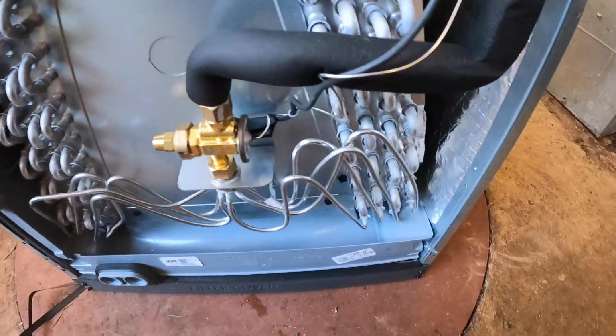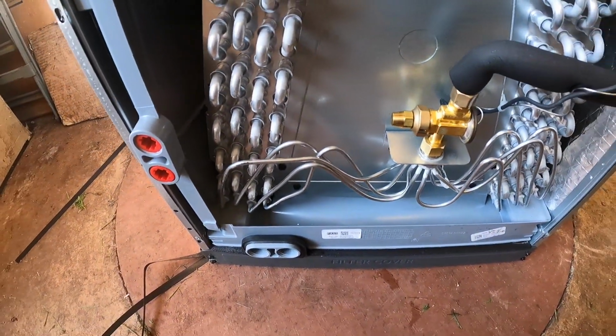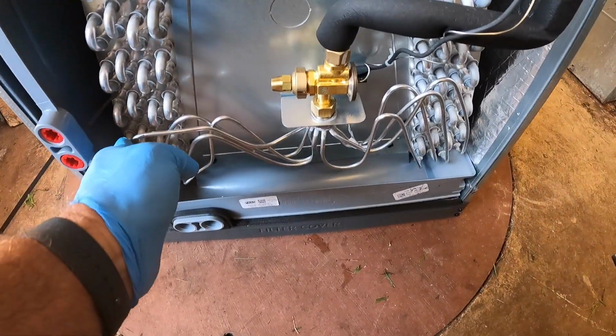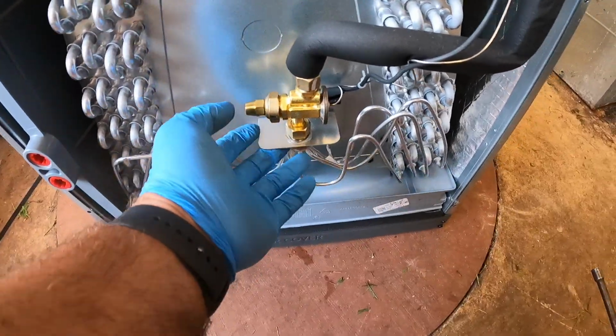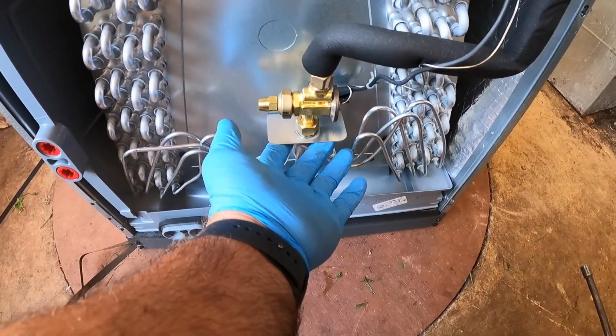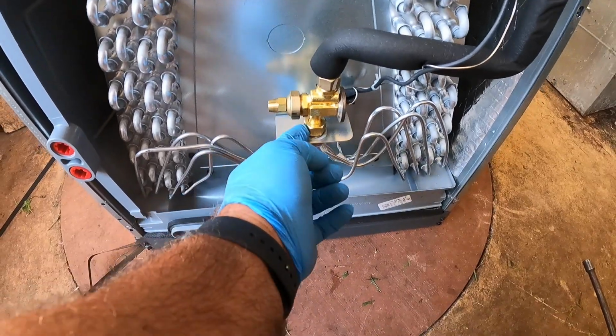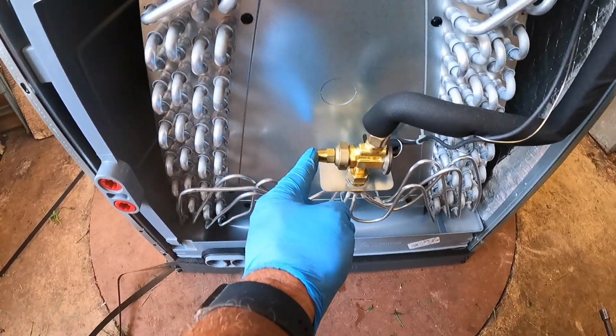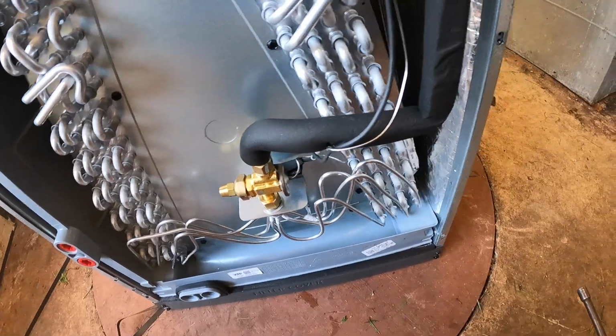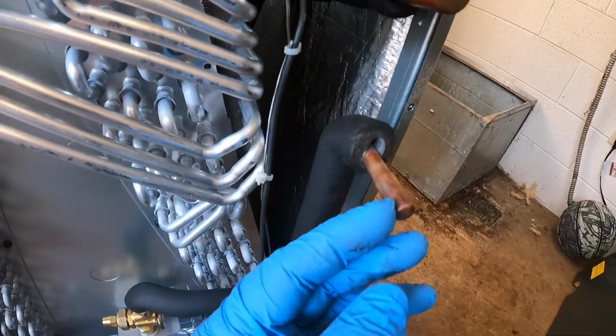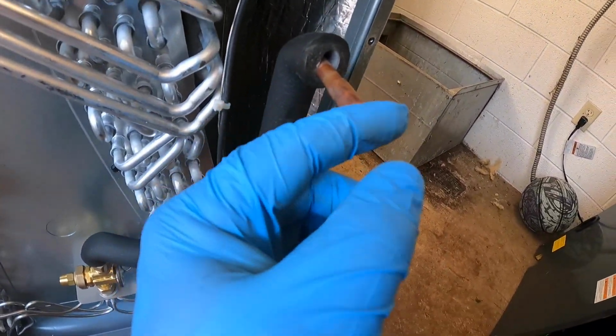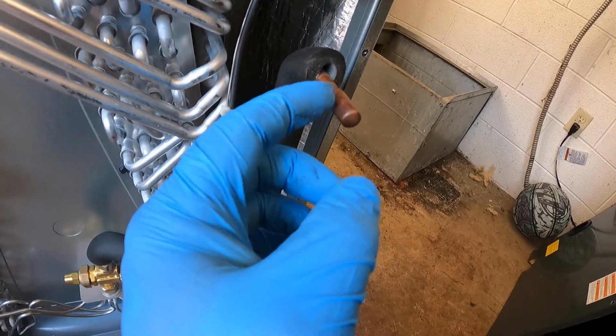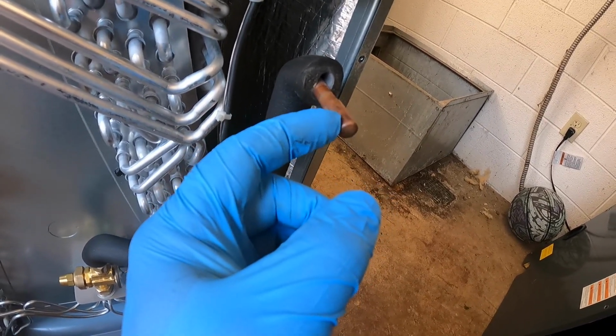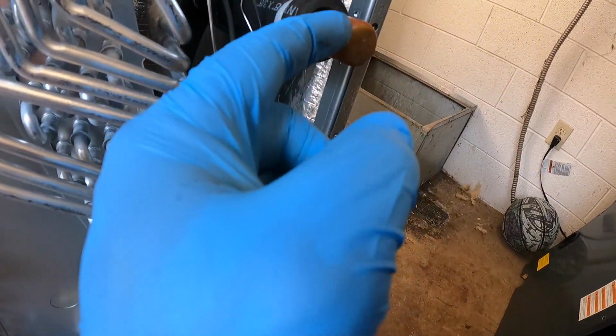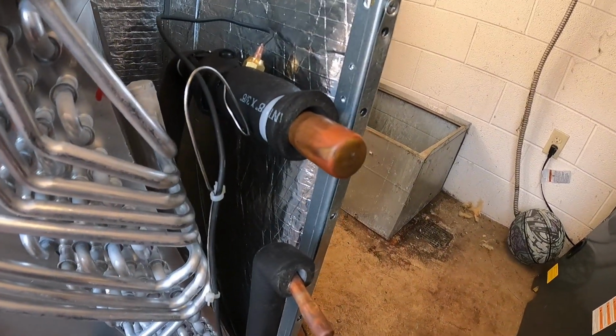Pretty nice and neat in here. They did a really good job with their little capillary tubes down here, small copper or small aluminum tubes. The TXV has the distributor mounted there, so the TXV screws right on top of it. Looks like it's got an adjustable TXV as well. I like these long spun ends on this. I'd rather have a rubber plug I could pull out, but they've made these extra deep, so once you cut it off, you still should have a pretty good socket.